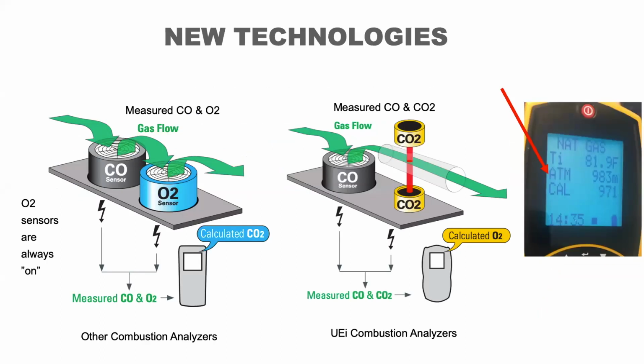So one of the other features, as I alluded to before, is that some combustion analyzers sense O2 or oxygen, and some sense CO2. So now we're going to talk about the difference, because you will find this in several models of the UEi combustion analyzers and it's really different and unique amongst all brands on the market. On the left-hand side here, you can see we measure CO and O2 in your combustion analyzer, and the electrical signals from those will come in and they'll be reported on the screen. And from the oxygen level and the fuel code that's given to the device, it will calculate the CO2 level.